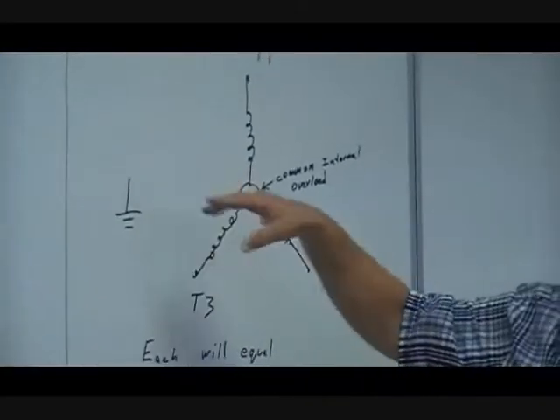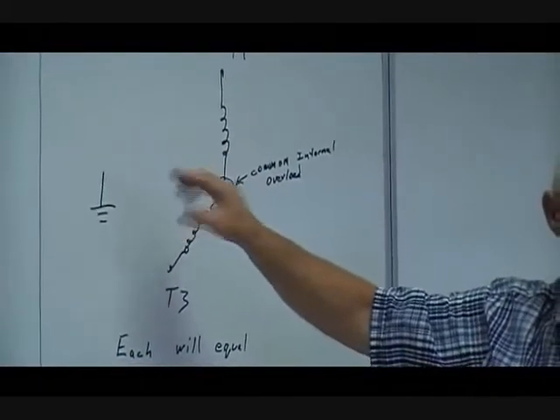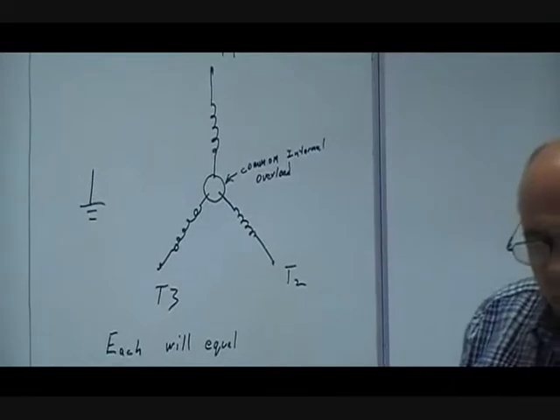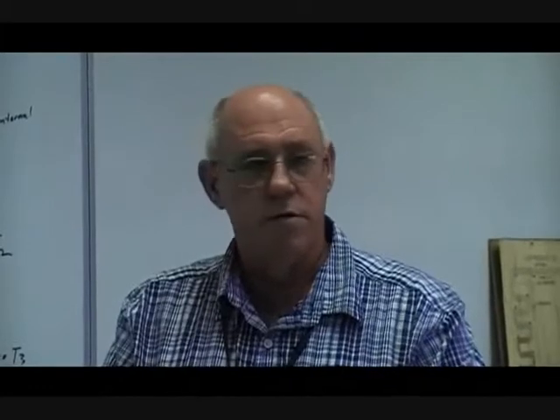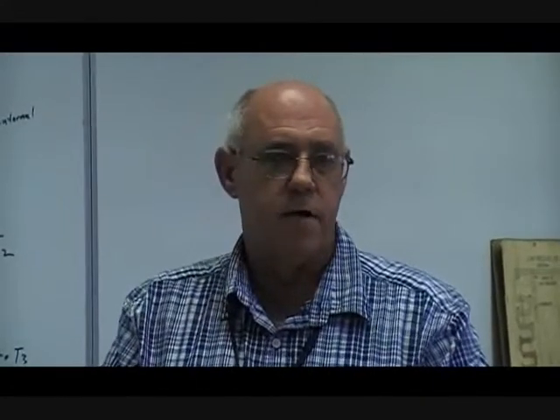You should not have any continuity to the case. There is a situation where, especially R22, if it's been sitting for a while, you may actually have some 50K ohms is not unusual to ground if it's been sitting for a while. But if I read less than that, a 50K to ground, I would be very, very skeptical about trying to run that compressor.